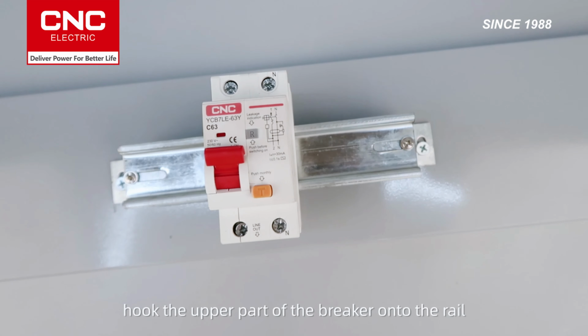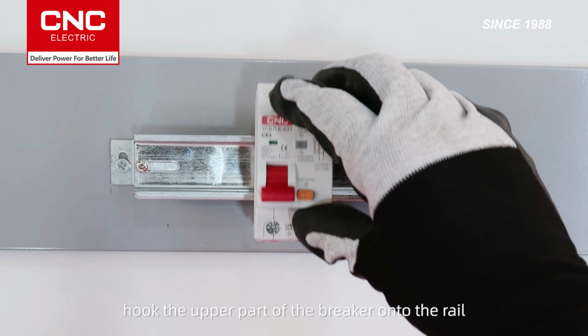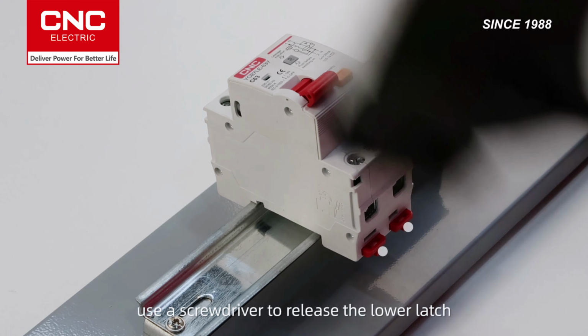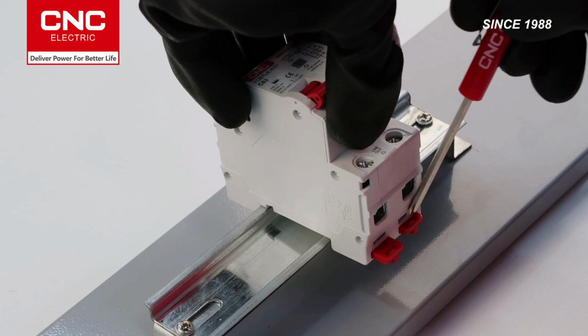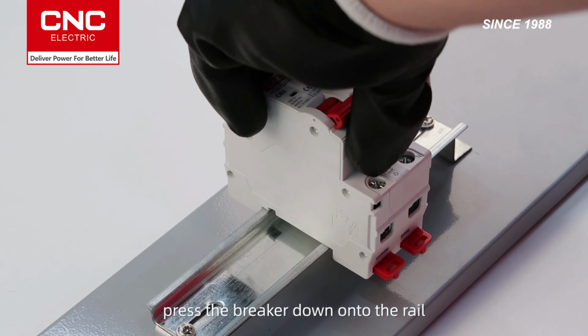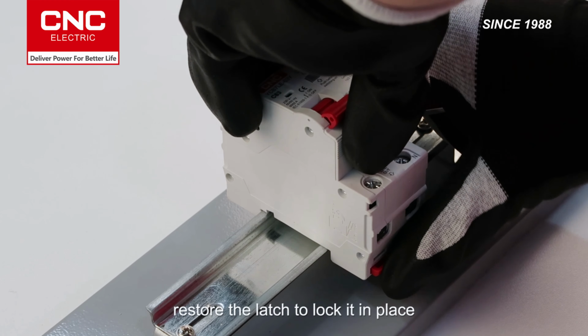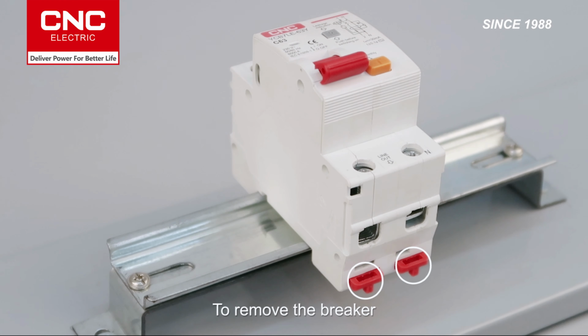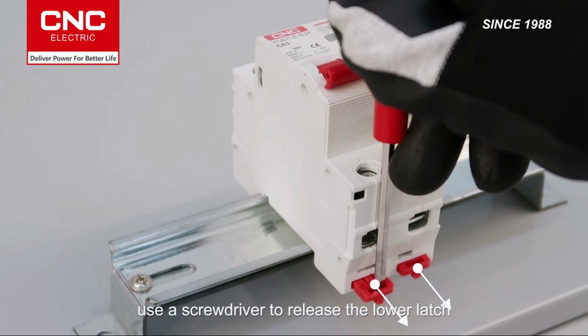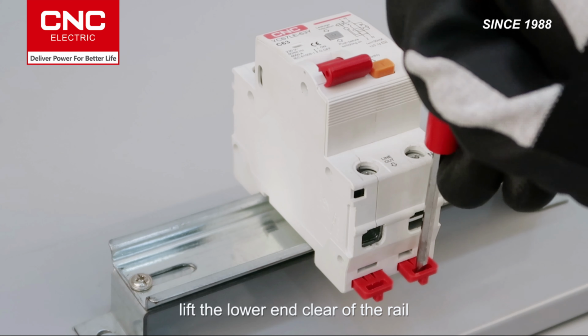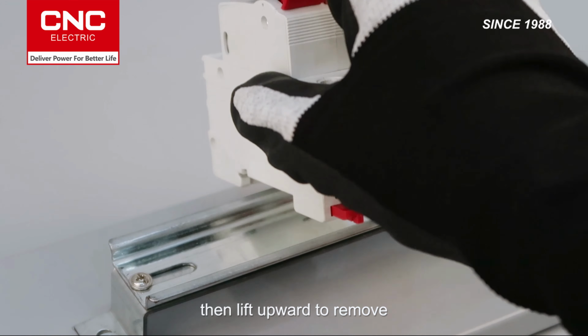Installation tip: hook the upper part of the breaker onto the rail. Use a screwdriver to release the lower latch. Press the breaker down onto the rail. Once seated, restore the latch to lock it in place. To remove the breaker, use a screwdriver to release the lower latch. Lift the lower end clear of the rail, then lift upward to remove.